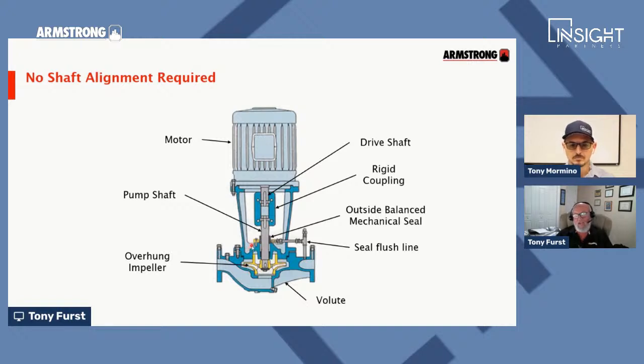The other advantage is where we have our shaft seal. Okay, we use an outside balanced mechanical seal. And if I take this coupling half off, and there's 4 to 6 bolts there that take the two coupling halves off, now I can come in here, I take the seal cap off, I can lift the seal out of the seal cavity, put the new seal in, put the cap back on, and I'm done changing the shaft seal in less than 30 minutes.